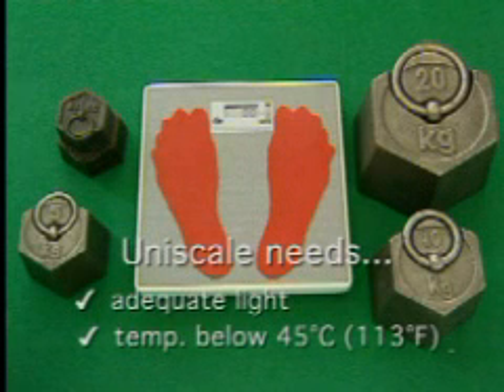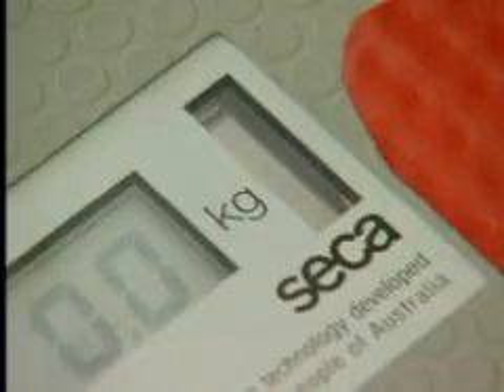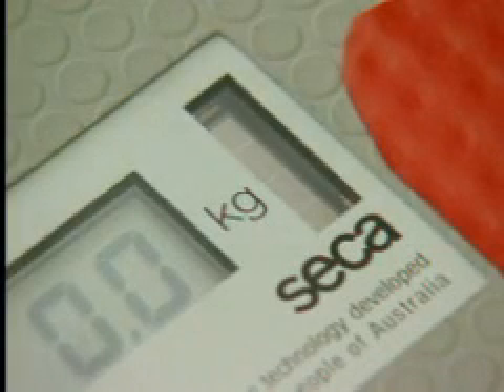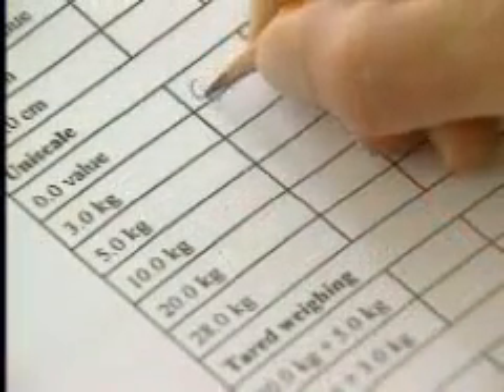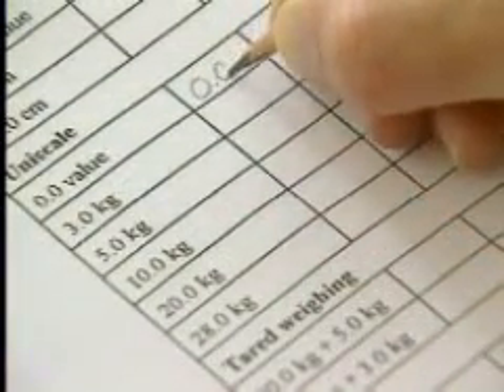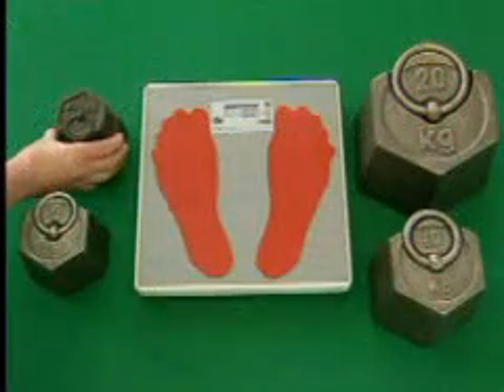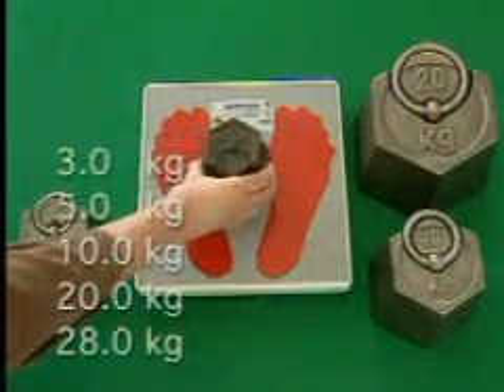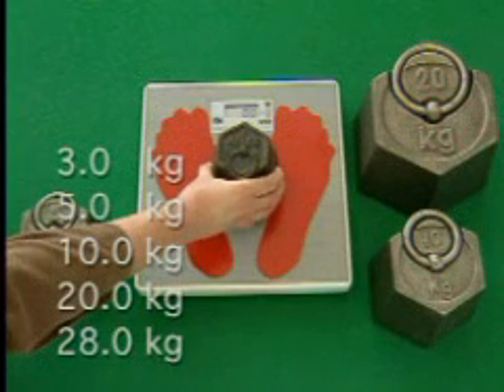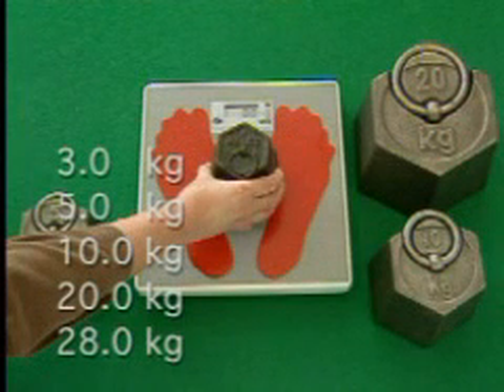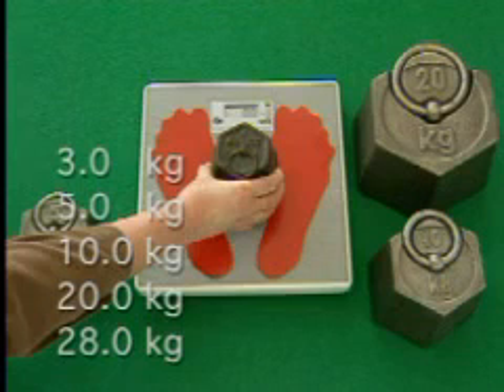In addition, there should be sufficient light to activate the solar panel. First, check that the value 0 is displayed after covering the solar panel for a fraction of a second. If it does, mark 0.0 on the calibration form. Successively weigh the test weights of 3.0, 5.0, 10.0, 20.0, and 28.0 kilograms and record the results on a calibration form.